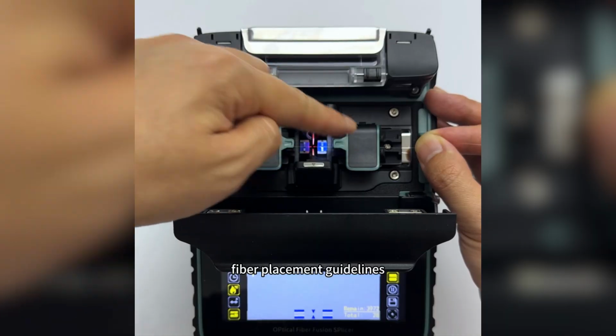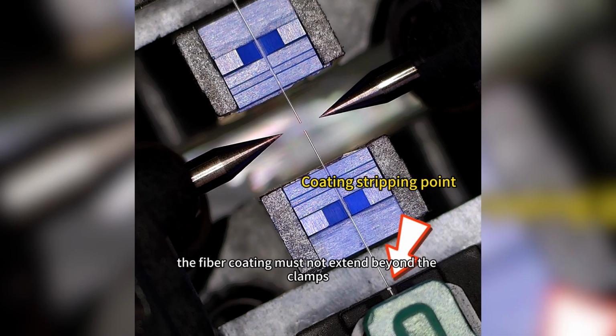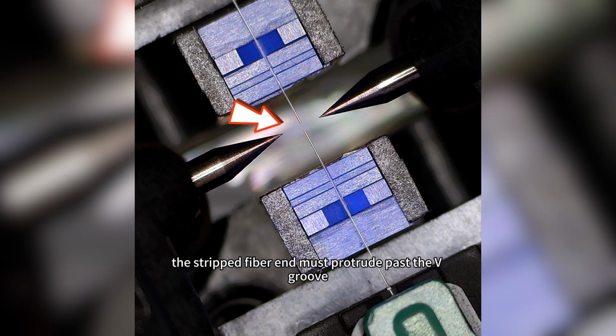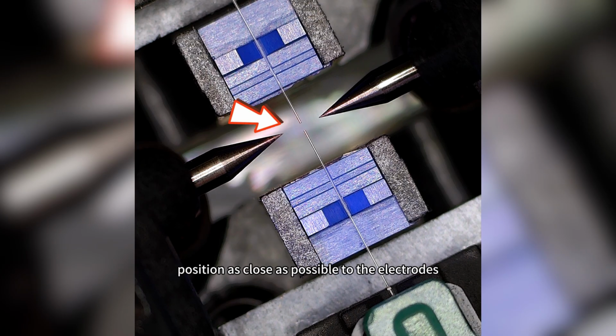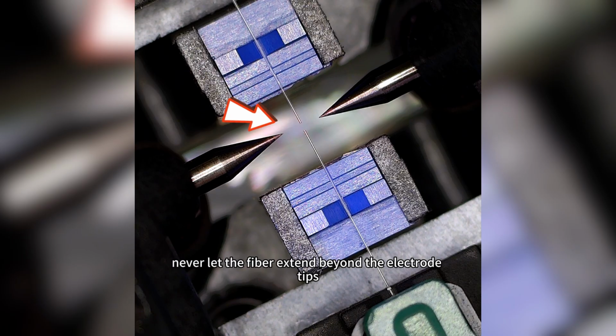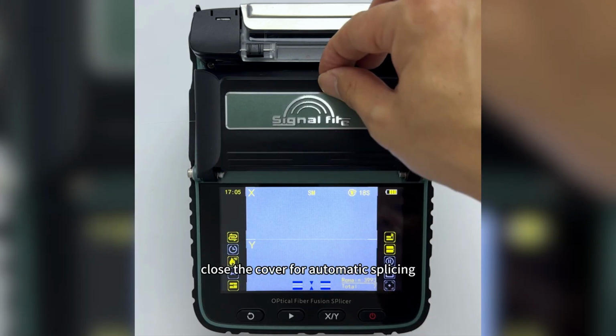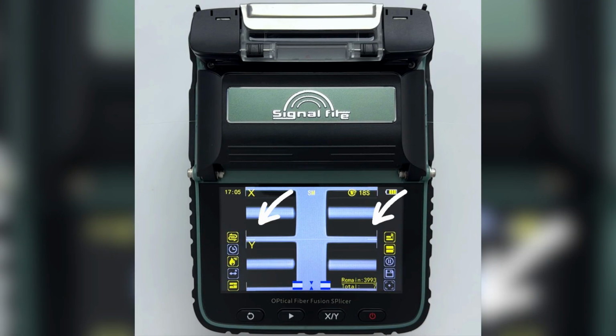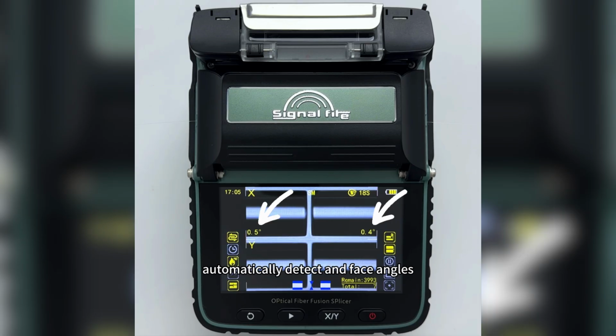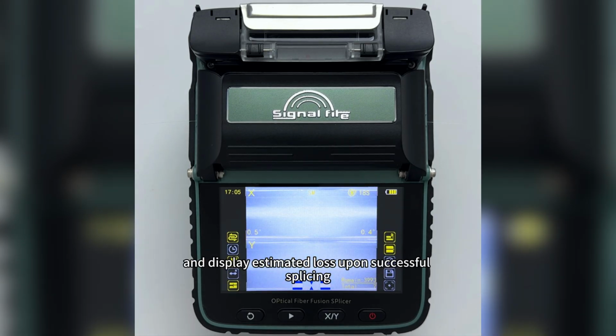Fiber placement guidelines. The fiber coating must not extend beyond the clamps. The stripped fiber end must protrude past the V-groove. Position it as close as possible to the electrodes, but never let the fiber extend beyond the electrode tips. Close the cover for automatic splicing. The device will automatically detect end face angles and display the estimated loss upon successful splicing.